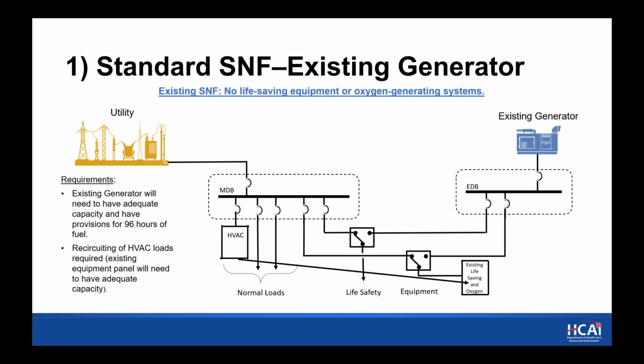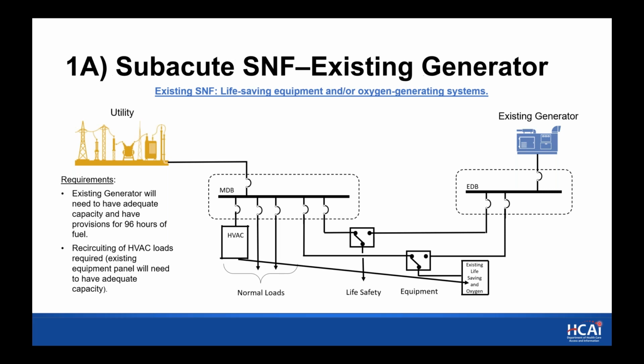And again, we're assuming that no life-saving and oxygen generator systems exist. Typically, we're going to see that the existing generators will not have 96 hours of on-site fuel storage, in which case you would need to make provisions to meet that requirement. So this would be an ideal situation if you have existing capacity on your generator. Next slide.